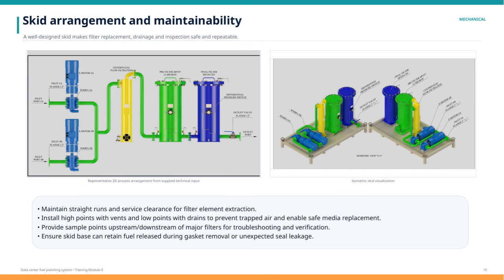High points should have vents to release trapped air, while low points must have drains to ensure proper drainage and safe media replacement. We also provide sample points both upstream and downstream of major filters to facilitate troubleshooting and system verification. Lastly, it's vital that the skid base is designed to retain any fuel that might be released during gasket removal or in the event of an unexpected seal leak. This helps contain spills and maintain a safe working environment. These considerations together enhance the maintainability and reliability of the fuel polishing system.